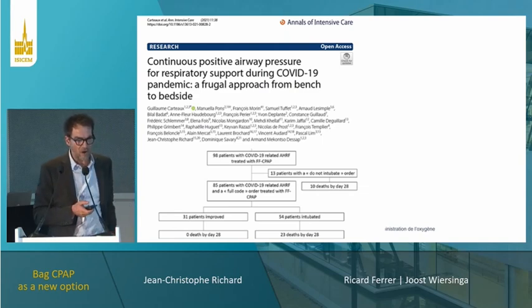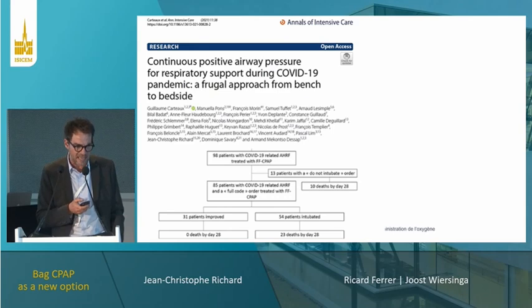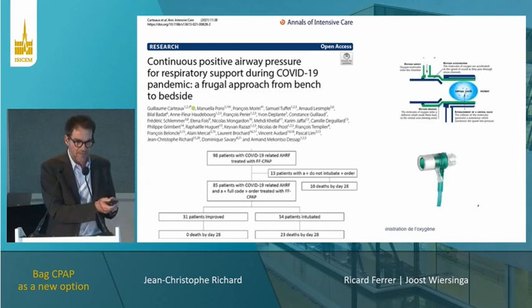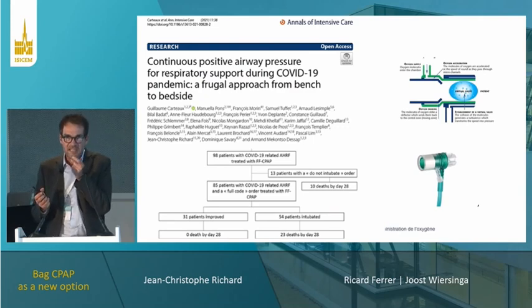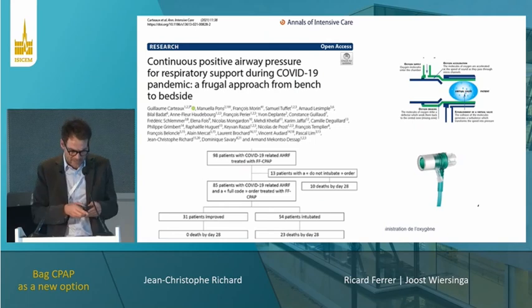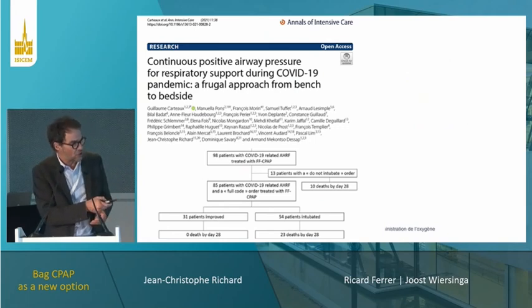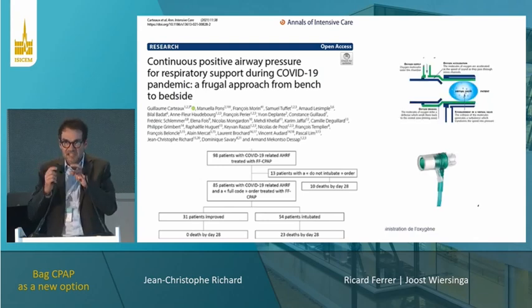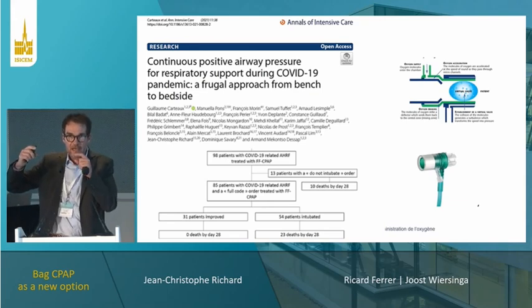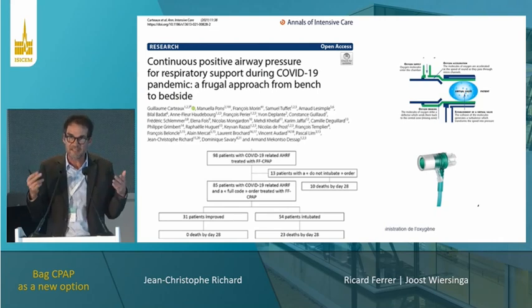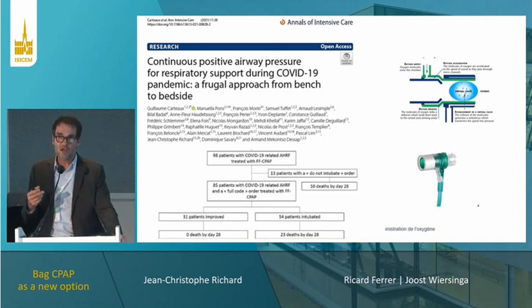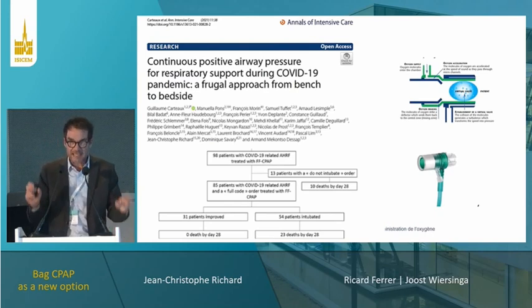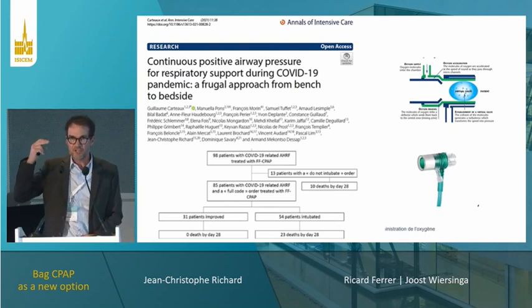So, with our colleagues of Henri Mondor Hospital, during the pandemic, we tested the possibility to use the Boussignac system, which is a very simple single-use CPAP, which is working as an open valve. There is a small illustration on the slide that shows you that the system is based on the connection to the flow meter, and because of the entrainment of ambient air, the system is able to increase the FiO2 and maintain a positive end expiratory pressure with a very low work imposed by the system, meaning that the system is very well tolerated by the patient, with the exception of the noise, which is very, very high.